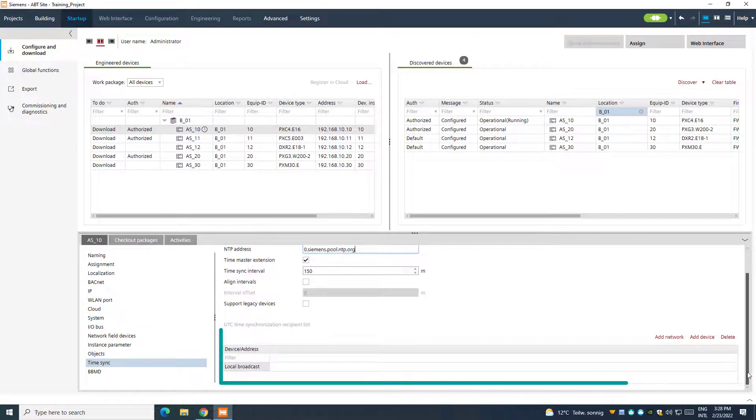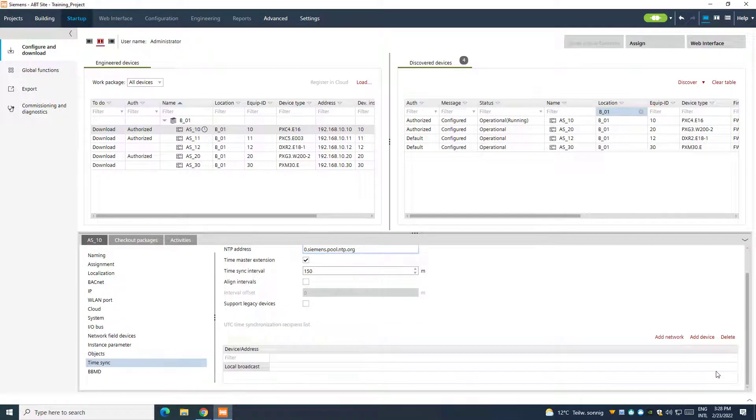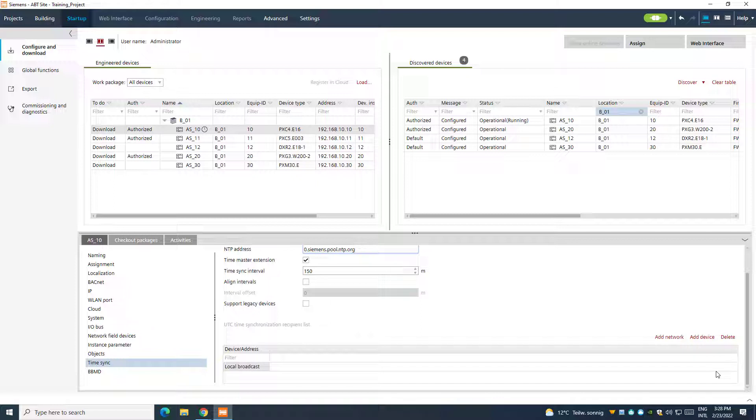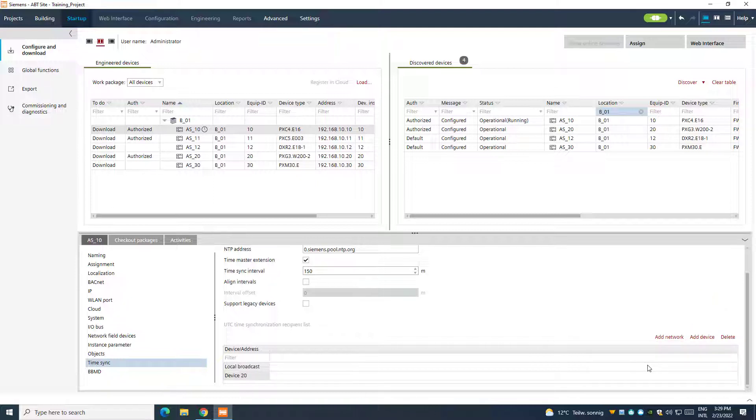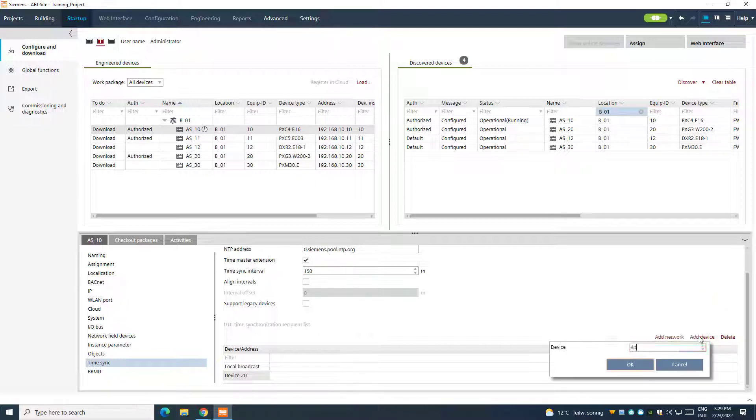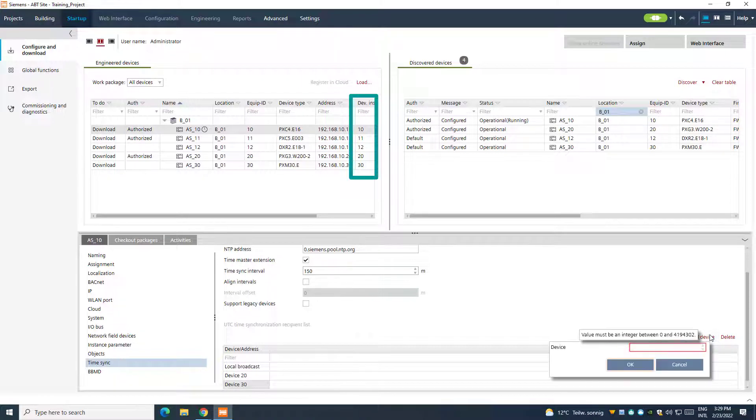In the UTC synchronization table, the local broadcast is automatically set, which means that all the devices of the PXC4 network will be synchronized. If we want to restrict the synchronization to just one or more devices, we can add a specific device instance number, which is available in the BACnet information of the device, or also in the specific column from the engineered device table.